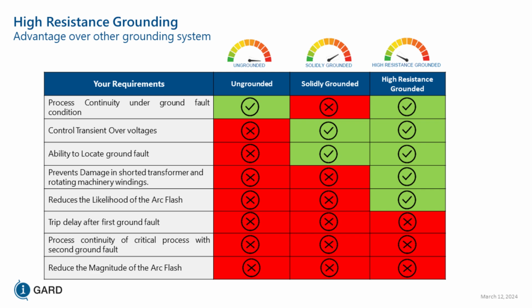So just ungrounded system, the only advantage an ungrounded system has is that you can have process continuity when there's a ground fault present. Solidly grounded system, you have control over the transient overvoltages and the ability to locate a ground fault. Obviously, you located the ground fault because the circuit breaker that was protecting that feeder tripped, and now you have to go look for a fault. But a high resistance grounded system gives you process continuity and control of transient overvoltages. You can locate where the fault is without shutting anything down.